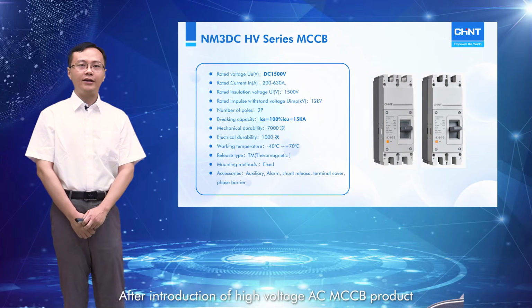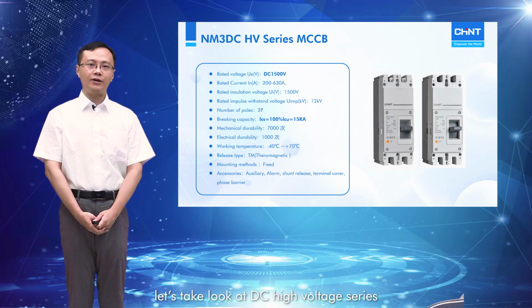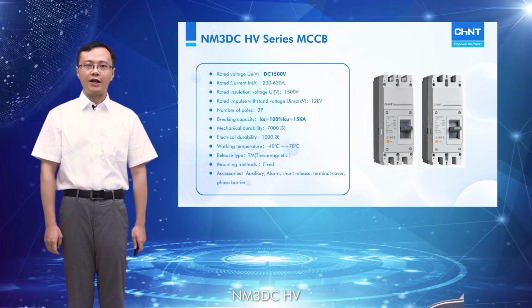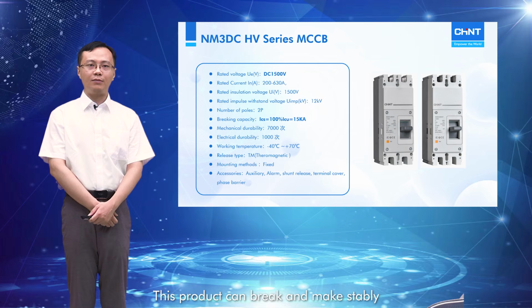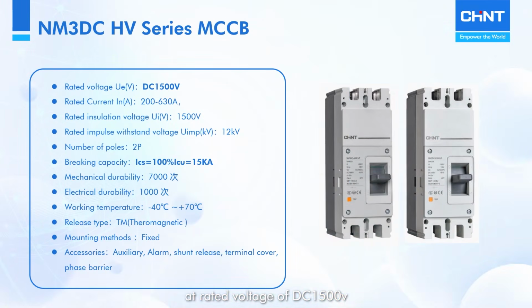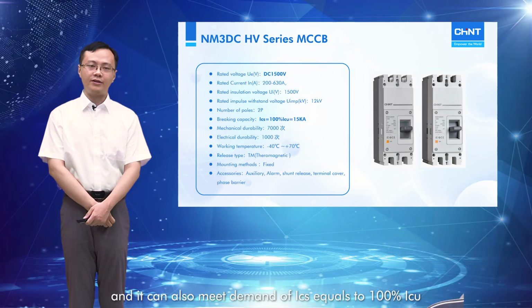After the introduction of the high-voltage AC MCCB product, next, let's take a look at the DC high-voltage series, NM3DC HV. This product can break and make stably at a rated voltage of DC 1500 volt with working current from 200 ampere to 630 ampere. It can meet the demands of most applications in centralized photovoltaic generation systems. The insulation voltage is up to 1500 volt and the impulse withstand voltage is 12 kV. To highlight, the number of poles is only 2, which greatly reduces the width of the product and saves installation space. It can also meet demands of ICS equal to 100% ICU.